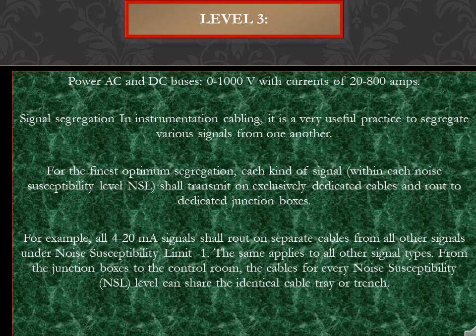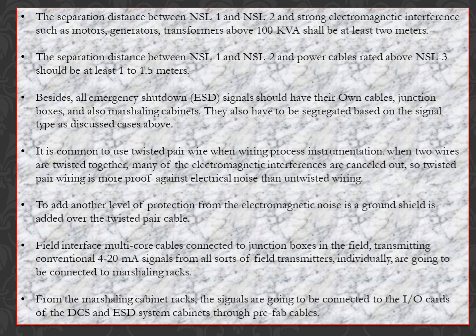From the junction boxes to the control room, the cables for every noise susceptibility level (NSL) can share the same cable tray or trench. The separation distance between NSL1 and NSL2 and strong electromagnetic interference sources such as motors, generators, and transformers above 100 kVA shall be at least 2 meters. The separation distance between NSL1/NSL2 and power cables rated above NSL3 should be at least 1 to 1.5 meters.